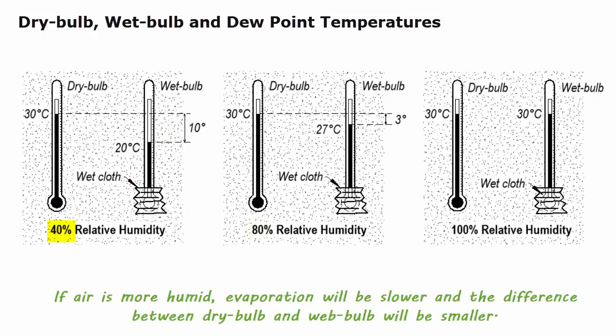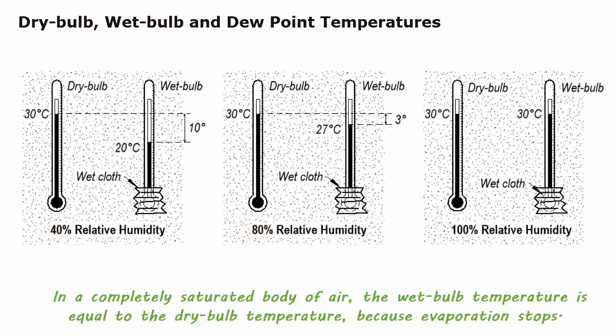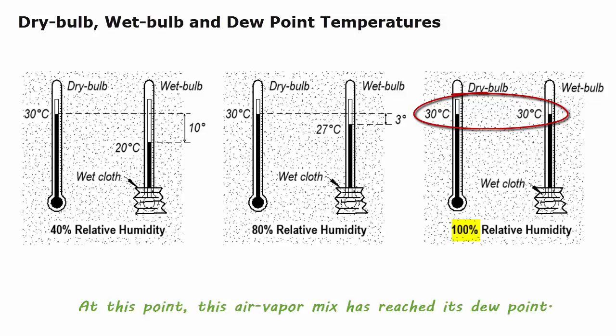If air is more humid, evaporation will be slower and the difference between dry bulb and wet bulb will be smaller. In a completely saturated body of air, the wet bulb temperature is equal to the dry bulb temperature because evaporation stops. At this point, this air-vapor mixture has reached its dew point.